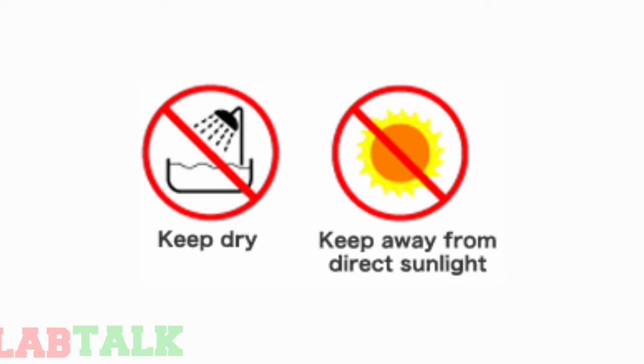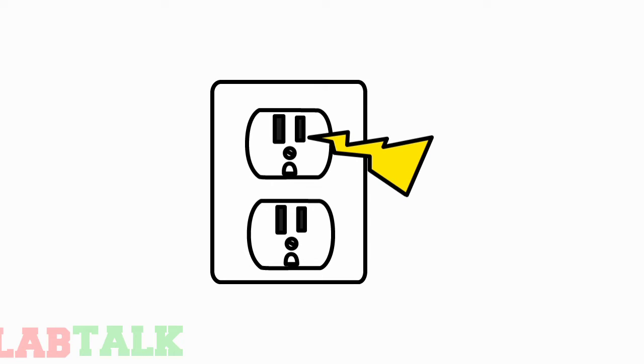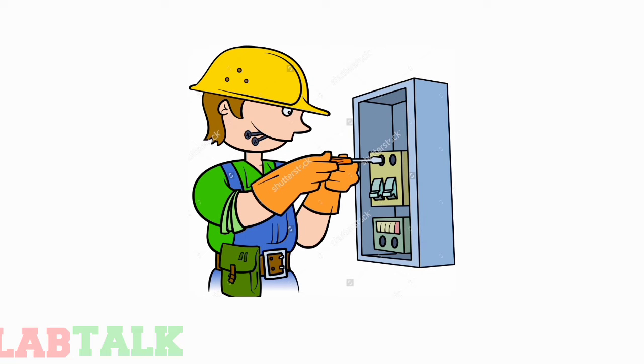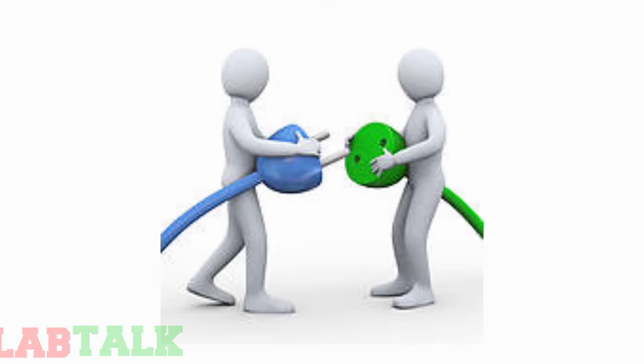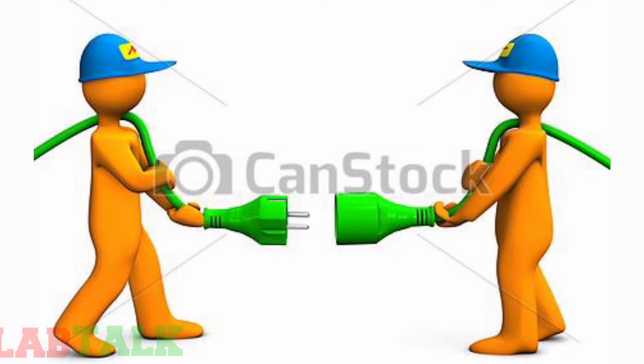Now, where to locate the equipment, that is, location. It needs to be located away from direct sunlight, other heat sources, and in an area free from draught. Locate equipment close to a power point so that there will not be any hanging wirings in the laboratory. Electrical: have the unit tagged and tested prior to use for electrical safety, and this can be conducted annually. Then check the connections. Connect to the power supply as marked on the serial tag. Check total wattage. Check sensors, whether they are in position and not damaged. Ensure all connections with sensors are secure.